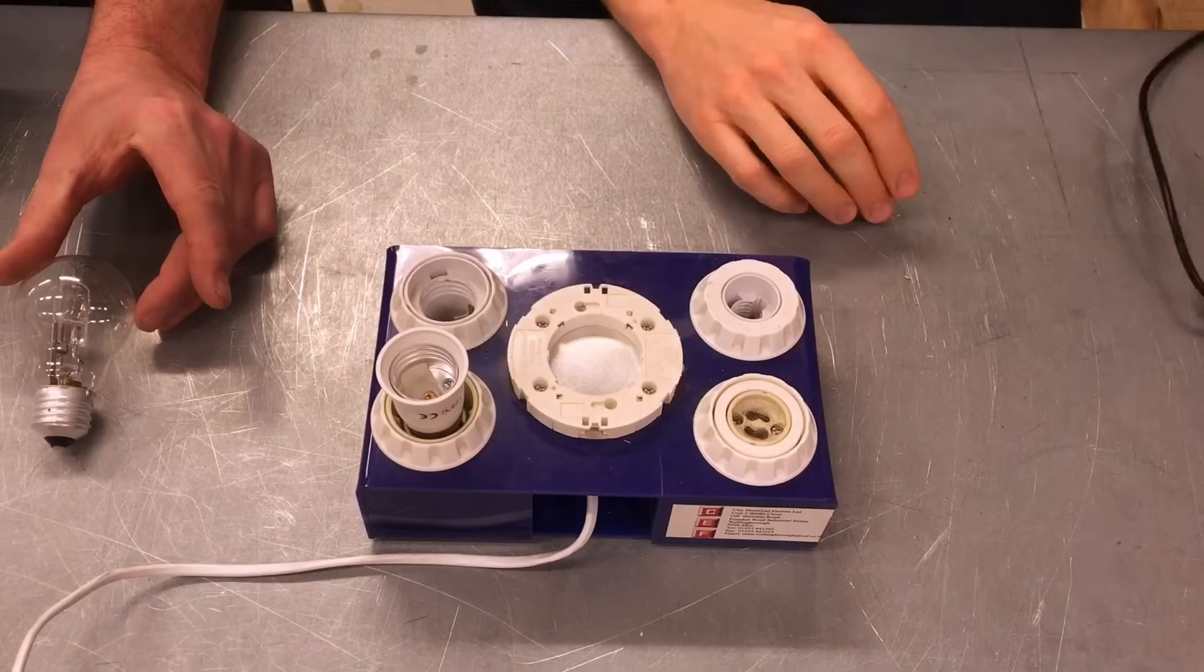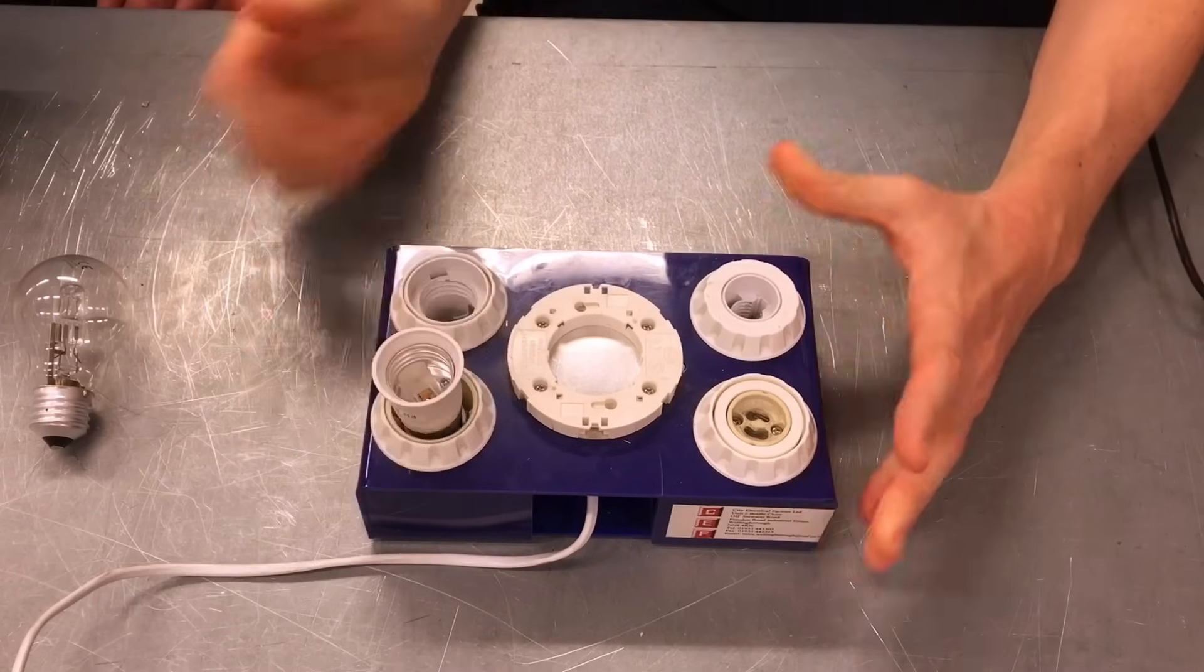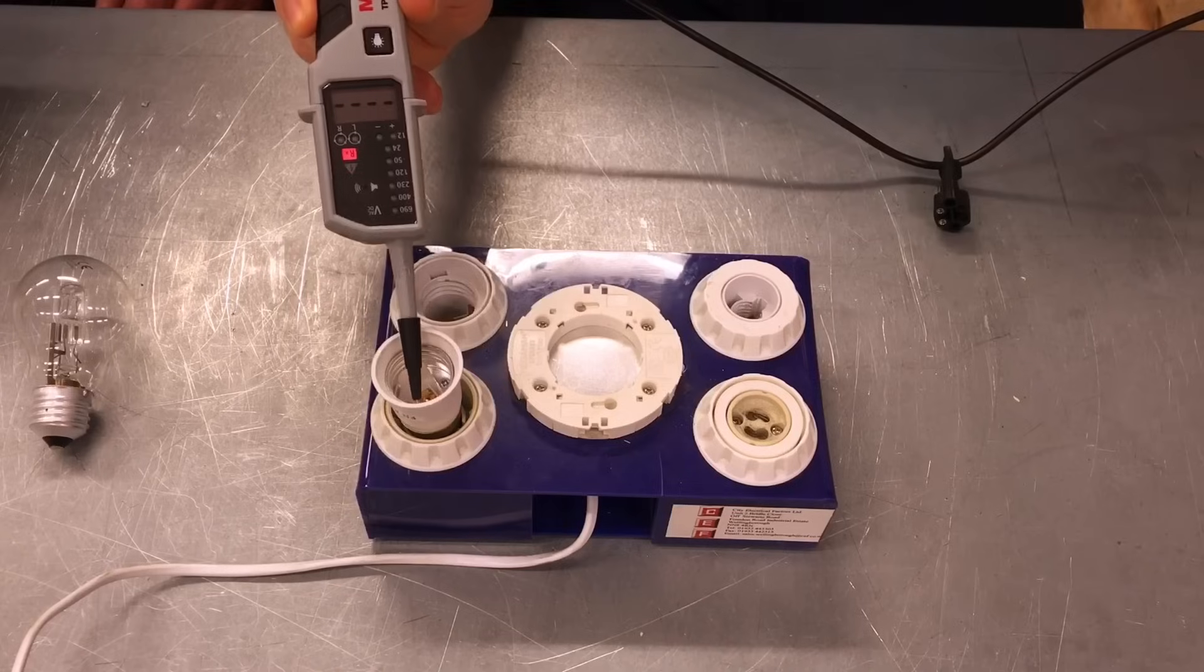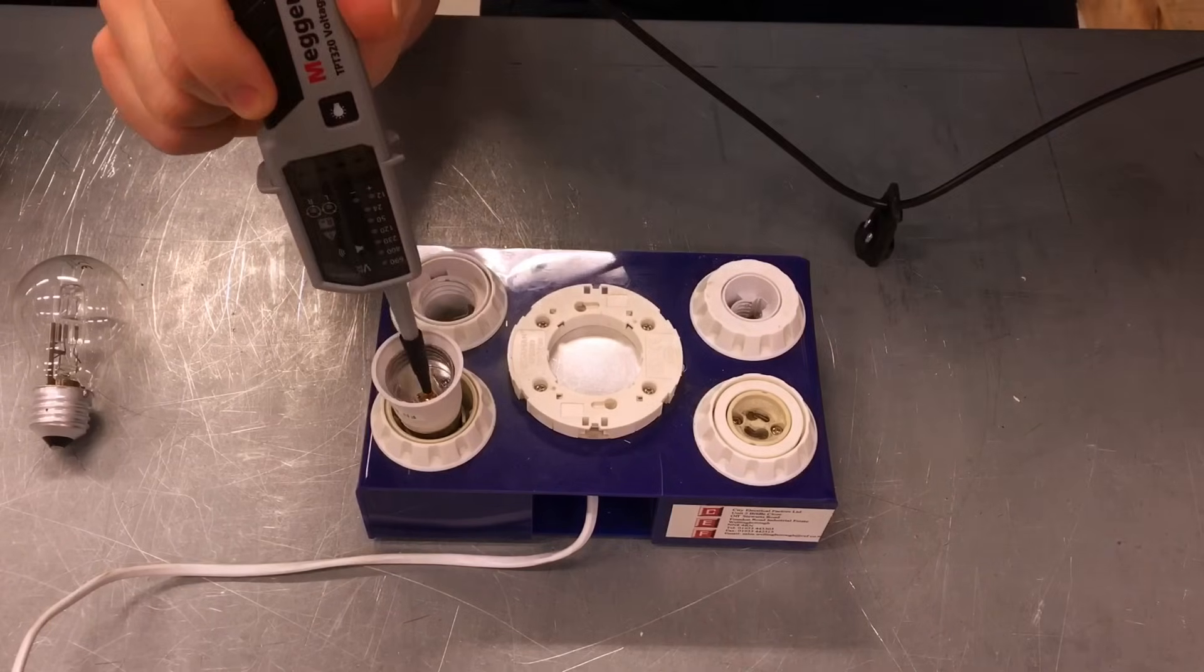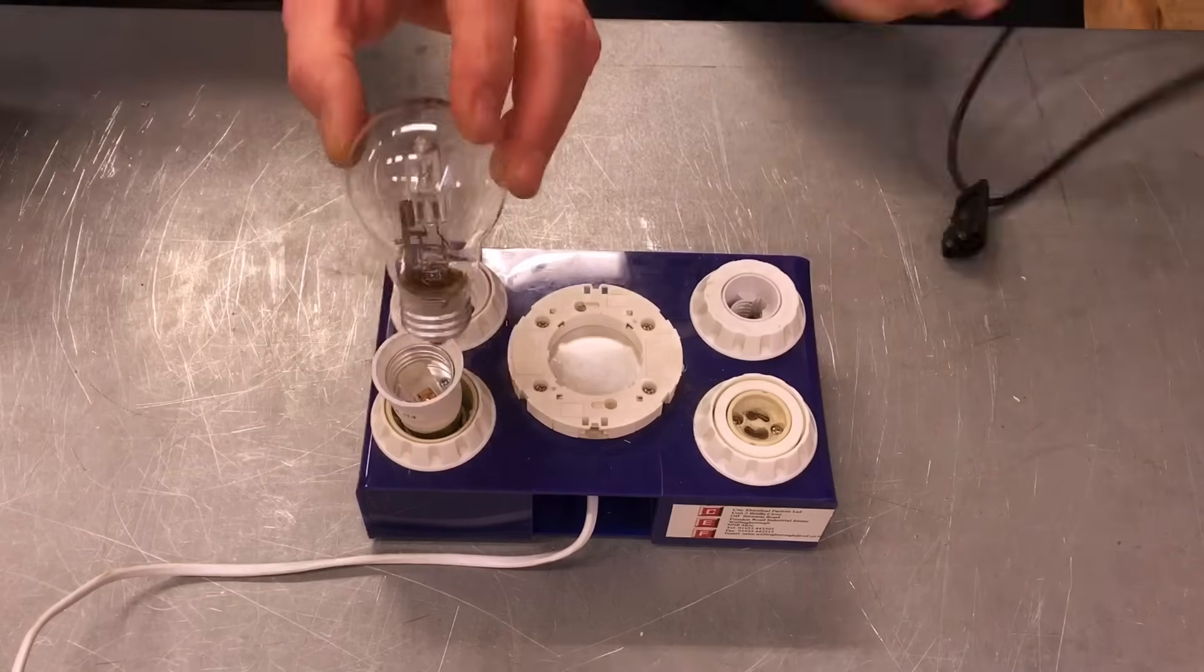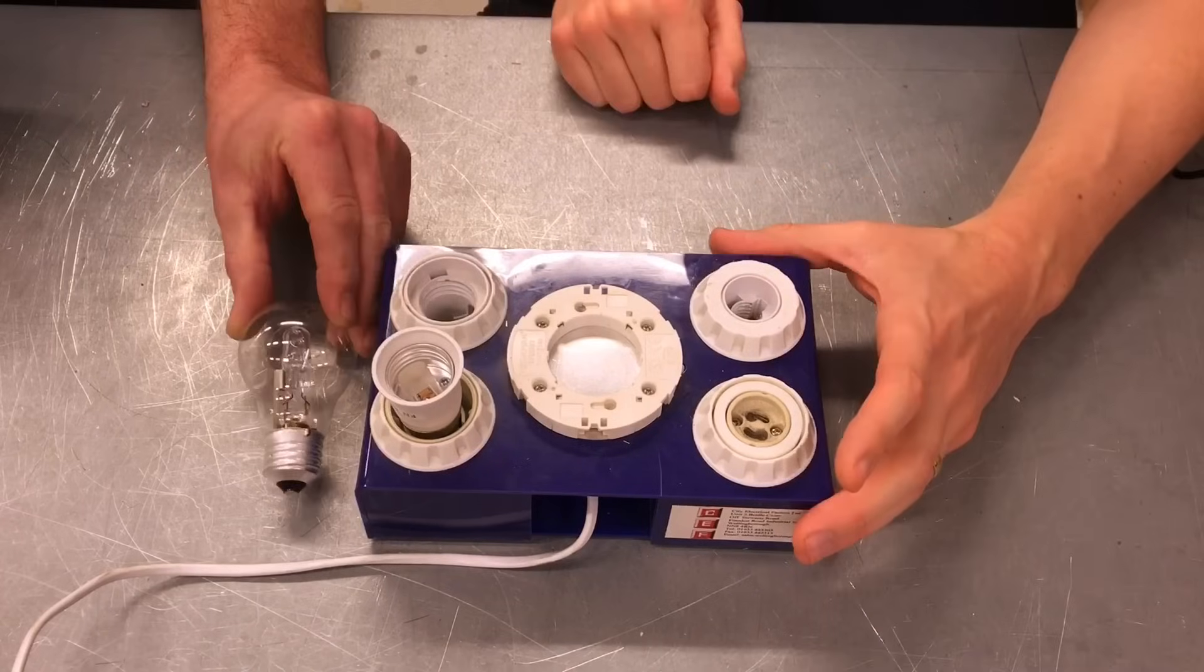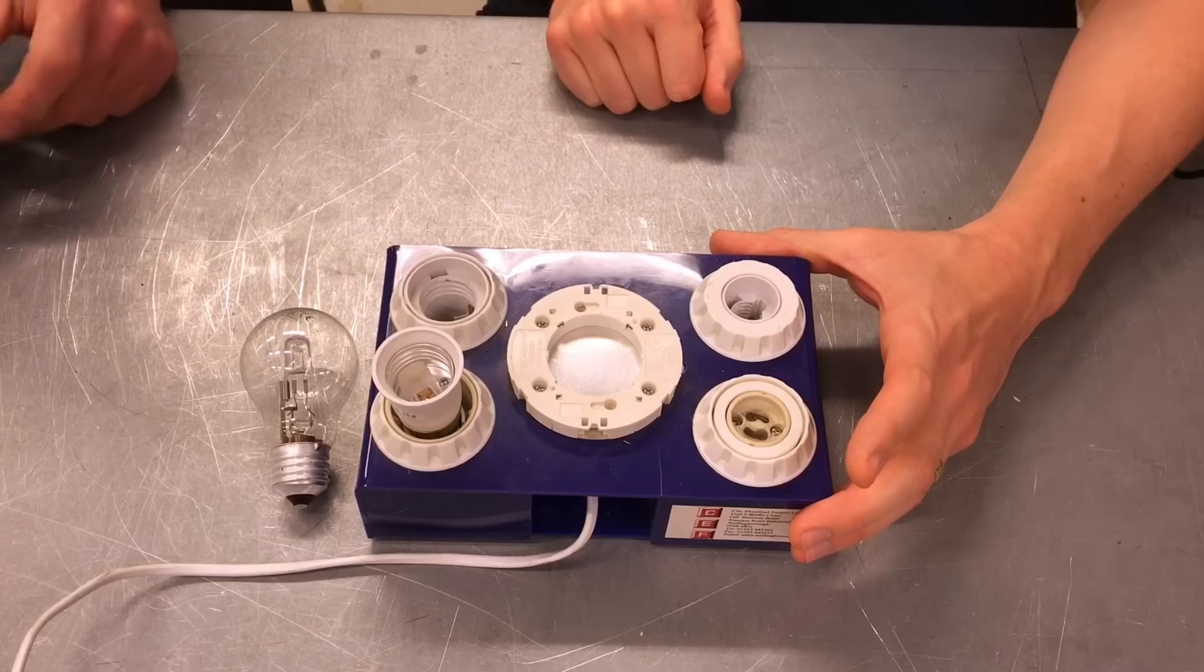So we're going to now change it round just to prove the point. So if we swap that over, turn it just 180 degrees. Again, we don't know which way round that is. If we now connect between earth and this outer, we've got nothing. Zero. We've got absolutely zero volts. But if we connect onto the center pin, you can see there we've got the line connection. So again, if I was doing it this time, the customer was super lucky and they started screwing it in and touched it there. No shock, because they're only connecting with a less dangerous neutral. 50% chance of, in the worst case scenario, killing yourself.